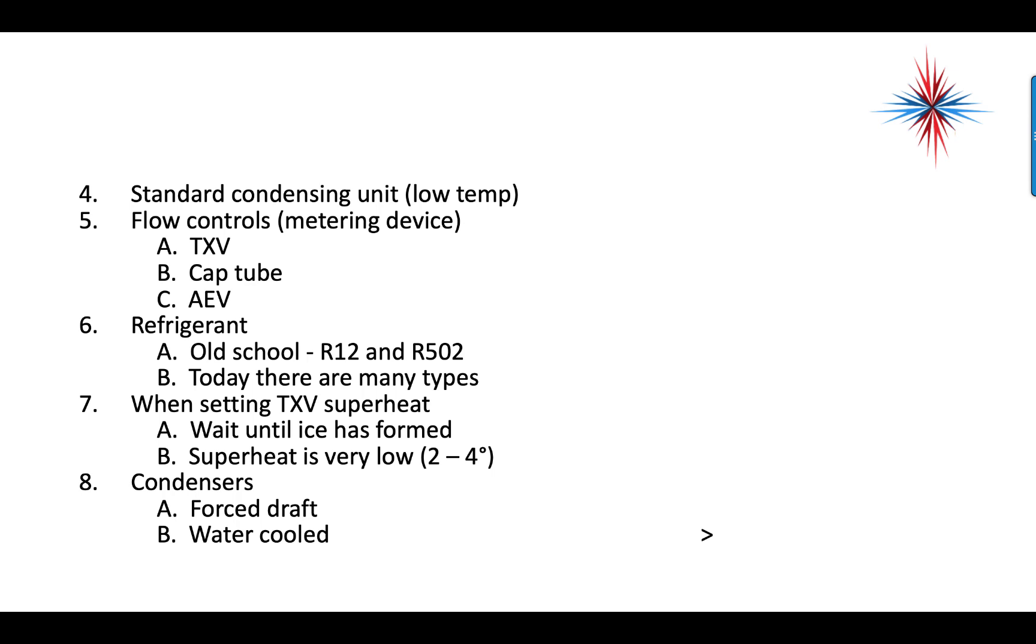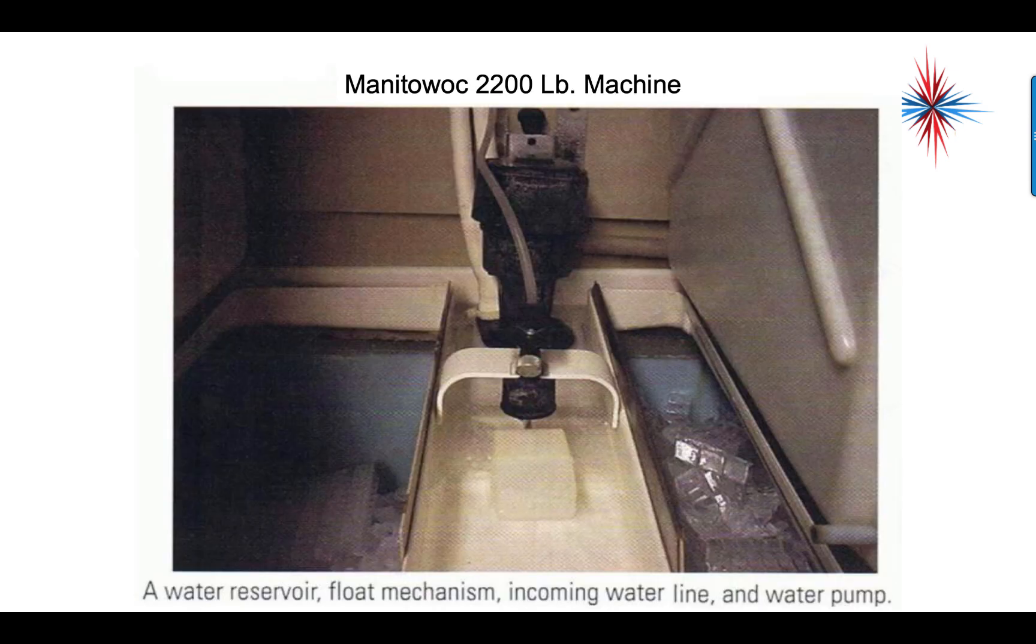When setting TXV superheat, you have to wait until the ice has formed. Superheat is going to be very low, 2 to 4 degrees. Condensers are usually forced draft or water-cooled.